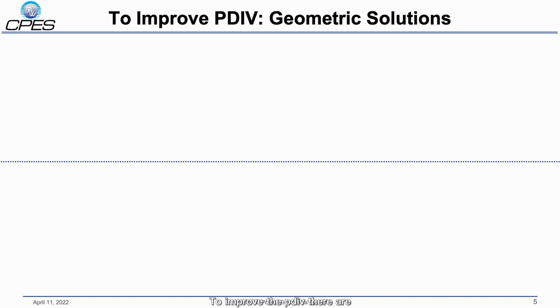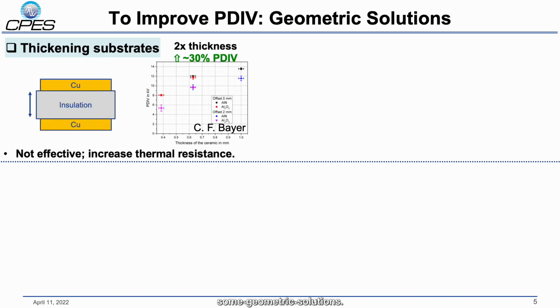To improve the PDIV, there are some geometric solutions. The first solution is thickening the substrate. By having thicker insulation of your substrate, you can have lower average electric field in your power module. But actually it is not very effective. By doubling the thickness of the insulation, one can only achieve about 30% of PDIV improvement. Besides, it also increased the thermal resistance a lot, because the most part of the thermal resistance in the power module actually is coming from the insulation of the substrate.